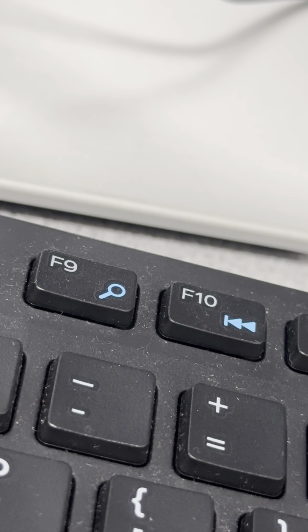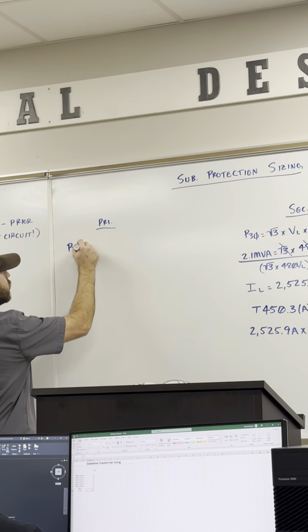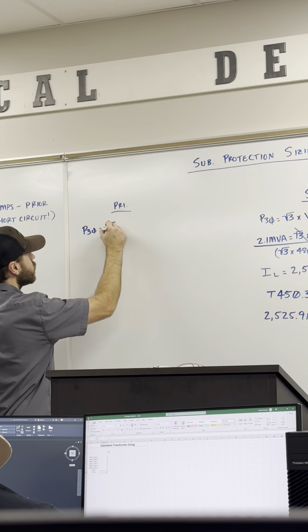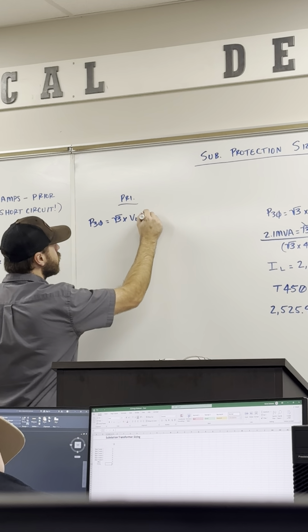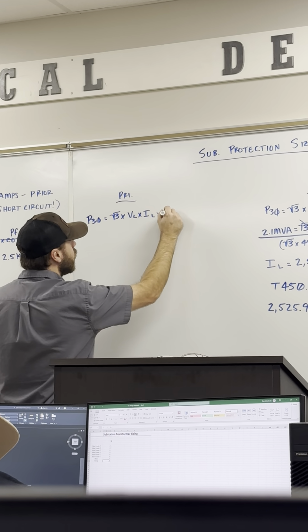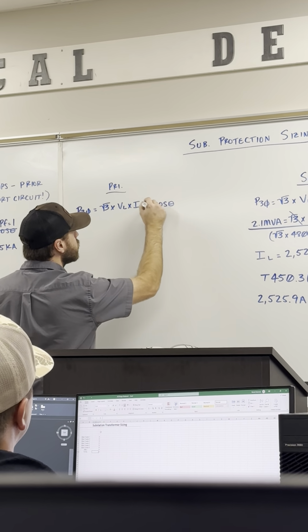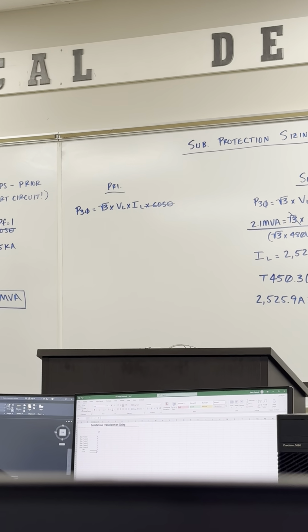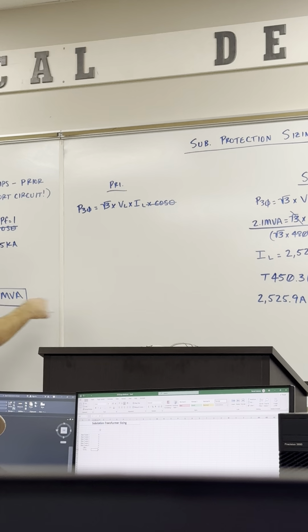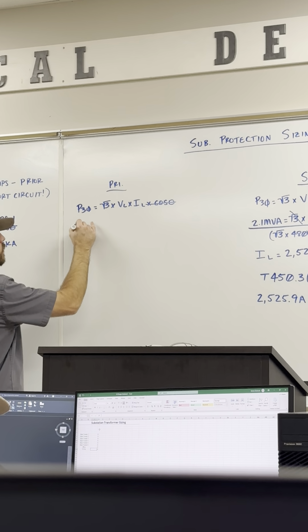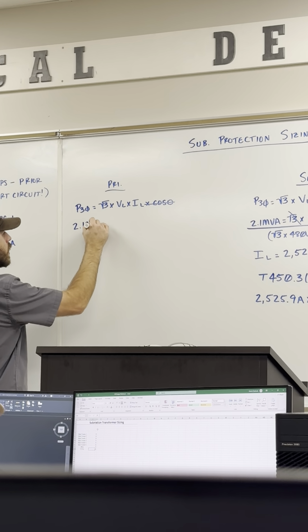Everybody's good with the secondary? All right, so that was our secondary breaker. We're basically going to do the exact same thing here on the primary. So we're still going to utilize that three-phase equation: square root of 3 times V line times I line times that cosine of theta. Again, we can drop off that cosine of theta. Our transformer size is not changing, so we still have 2.1 MVA.